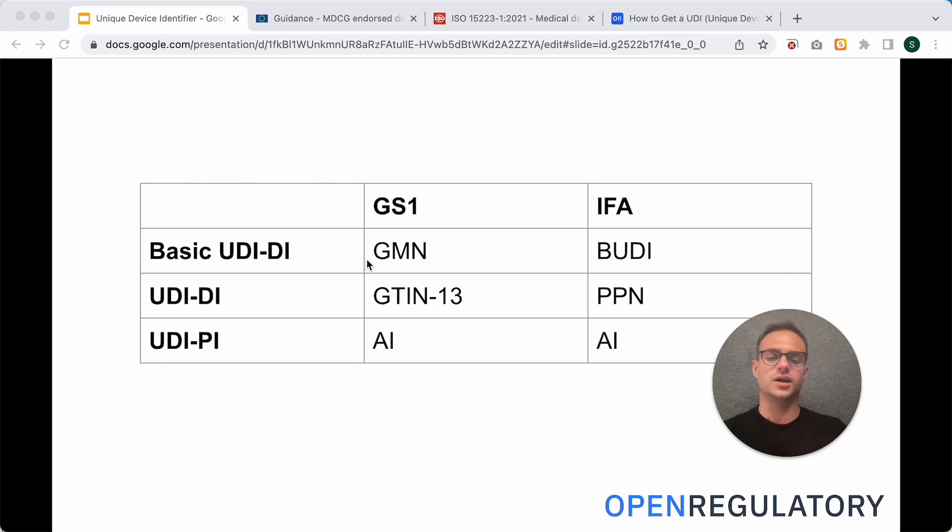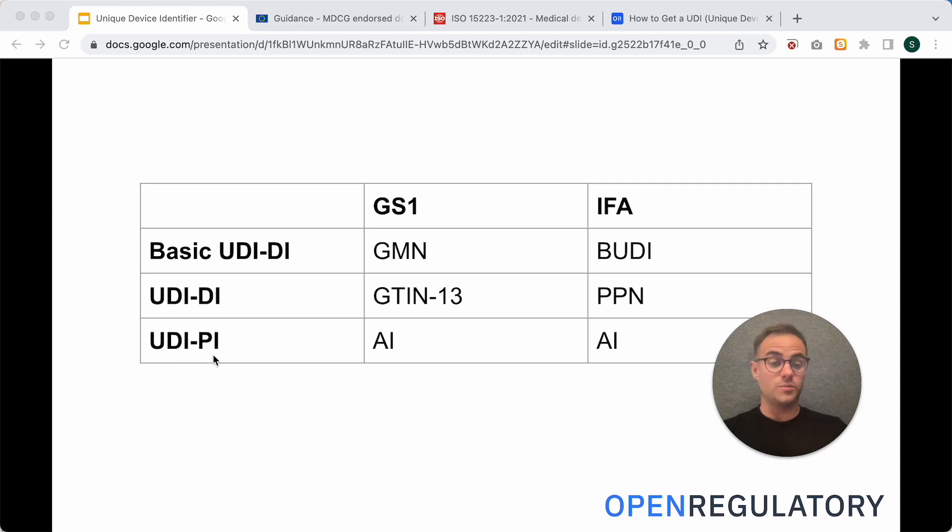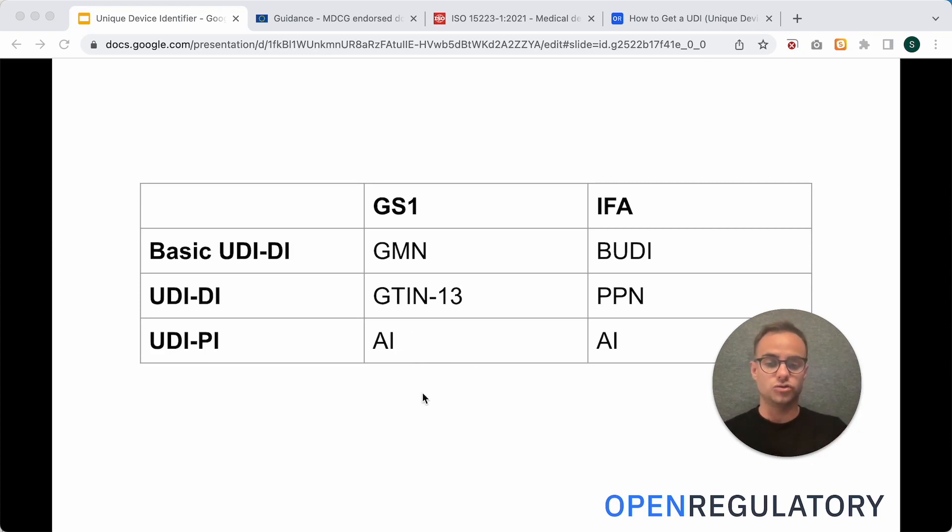So, the basic UDI-DI is the GMN, and the UDI-DI is the GTIN-13. The UDI-PI, as I said, you can make up yourself, but from this numbering system, there are certain rules how to actually come up with this number. I will explain that later.